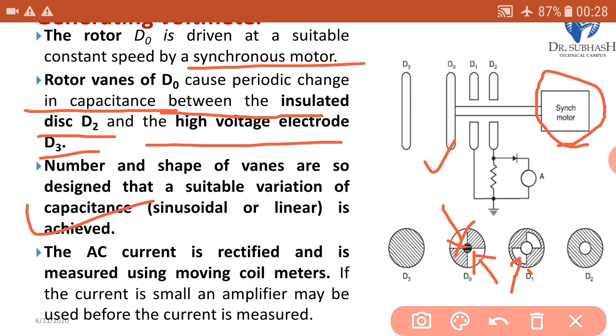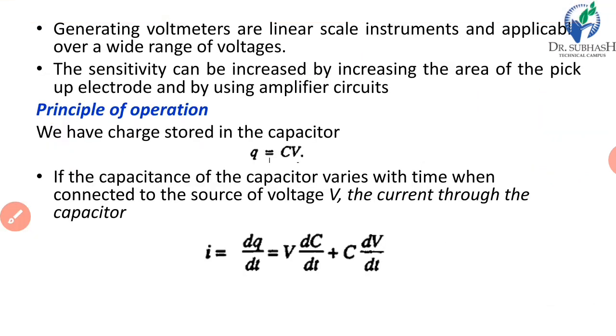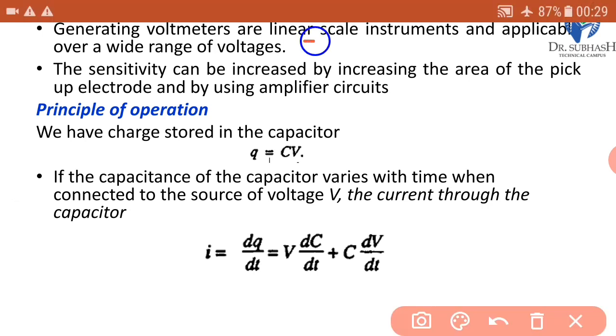The AC current is rectified and is measured using moving coil meters. Here is a meter, and it is a moving coil type ammeter. If the current is small, an amplifier may be used before the current is measured. So if the current is very small, then we have to use an amplifier for magnifying the current. Generating voltmeters are linear scale instruments and applicable over a wide range of voltages. The sensitivity can be increased by increasing the area of the pickup electrode and by using amplifier circuits. So by using these we can increase the sensitivity of this instrument.